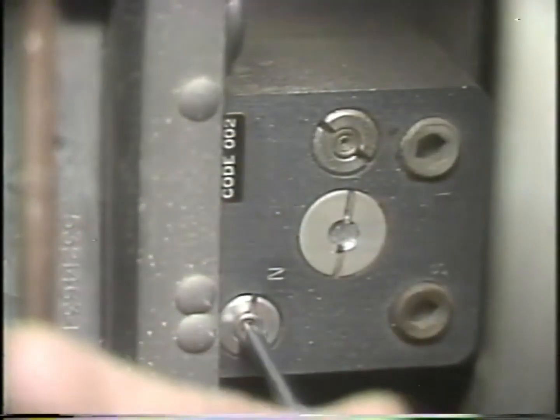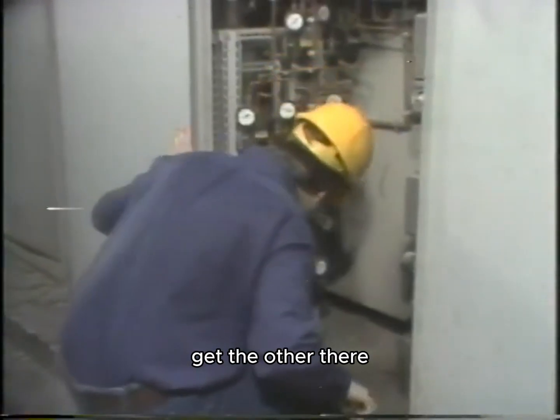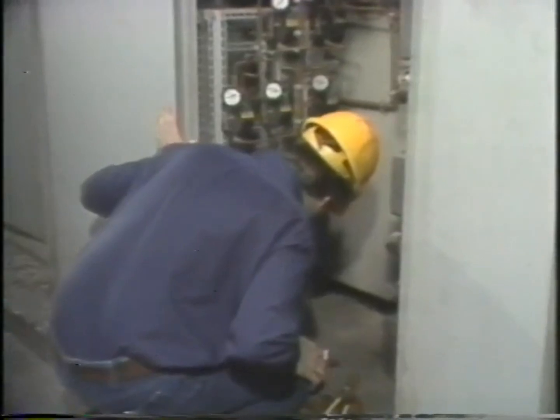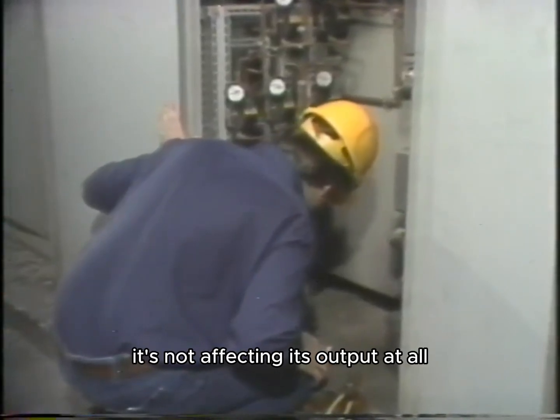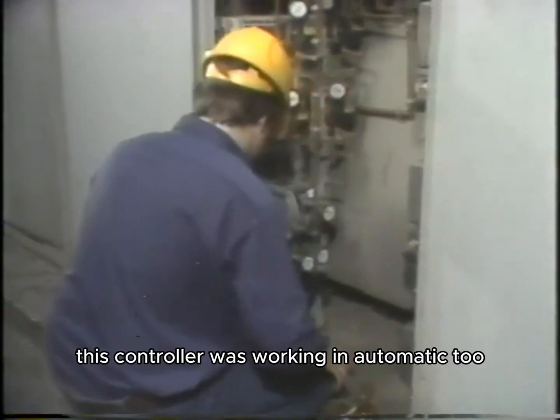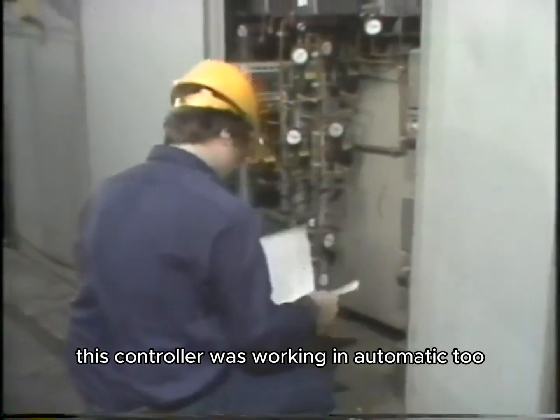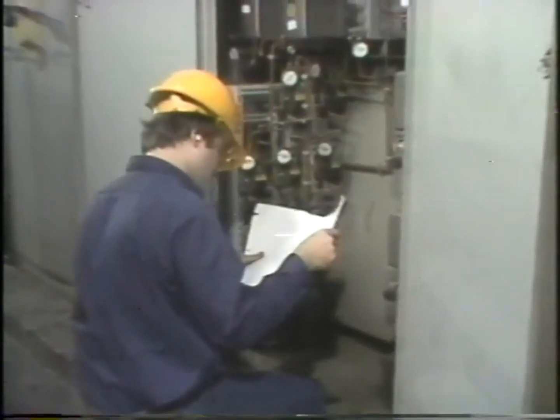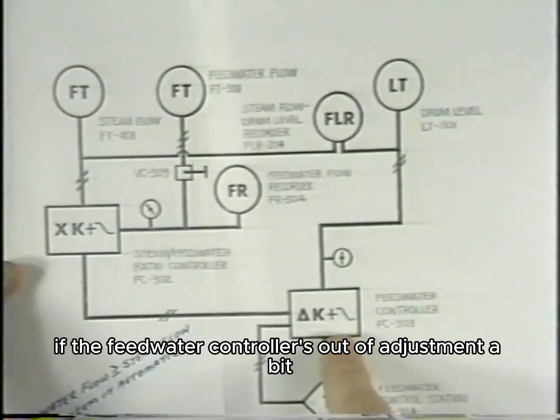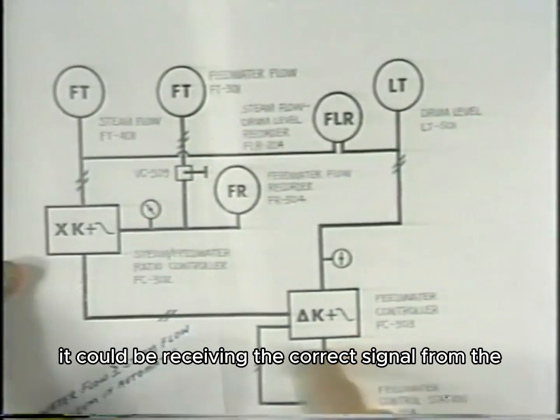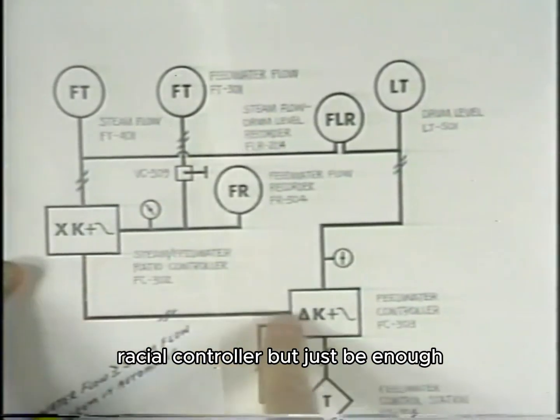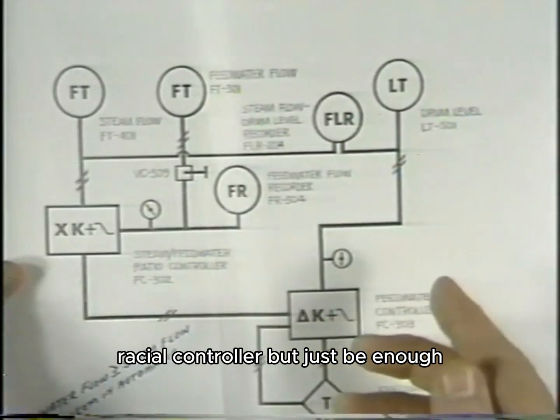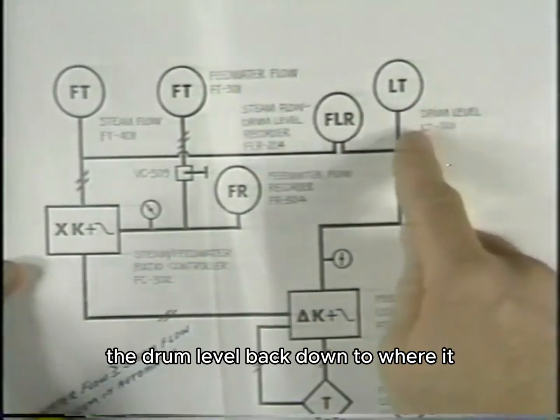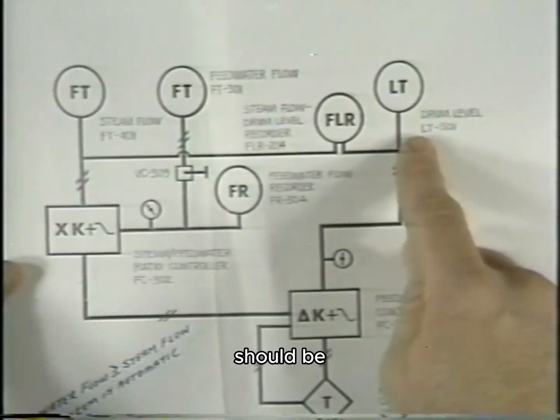That's one. Let me get the other. There. Yeah, it's not affecting its output at all. This controller was working in automatic too, just like the ratio controller. You know, if the feed water controller is out of adjustment a bit, it could be receiving the correct signal from the ratio controller, but just be enough out of adjustment so that it won't bring the drum level back down to where it should be.